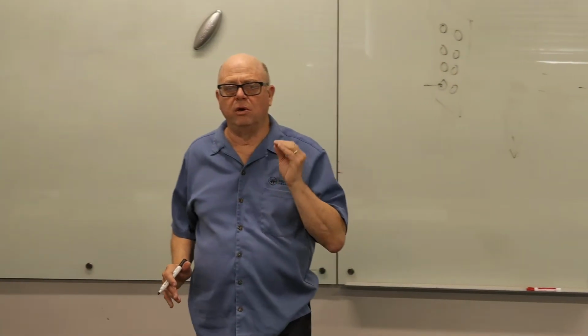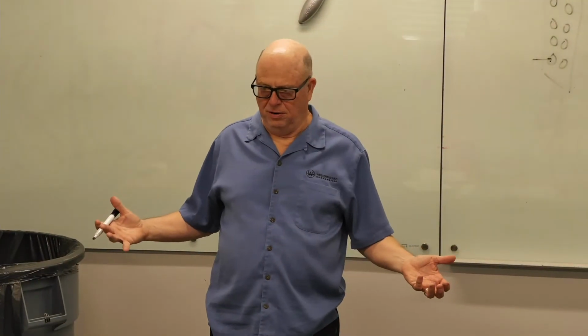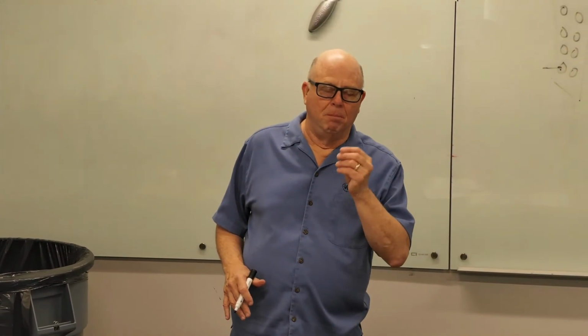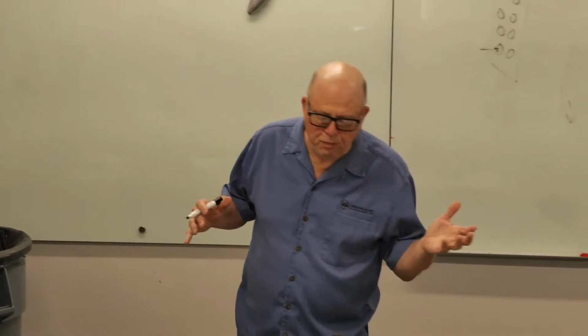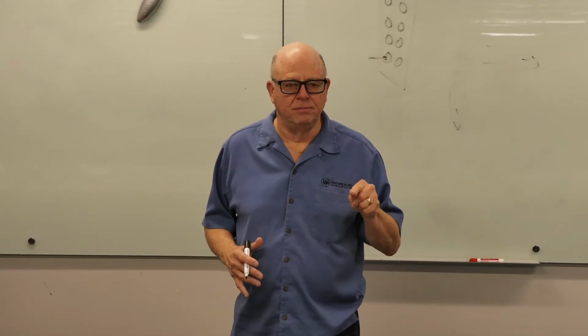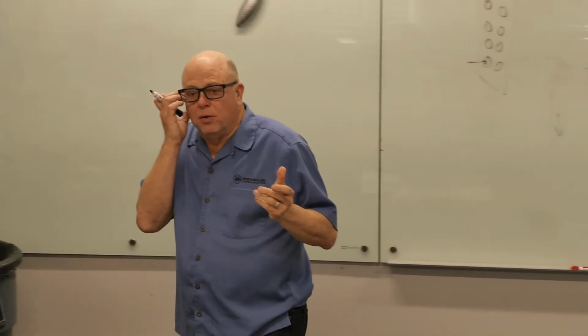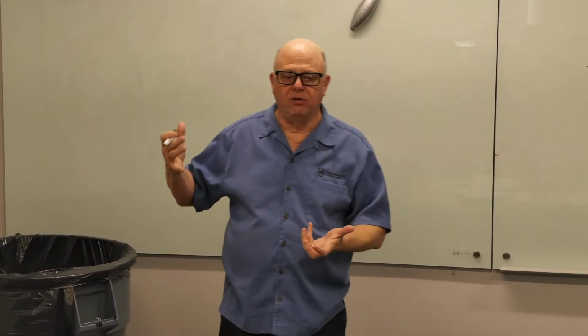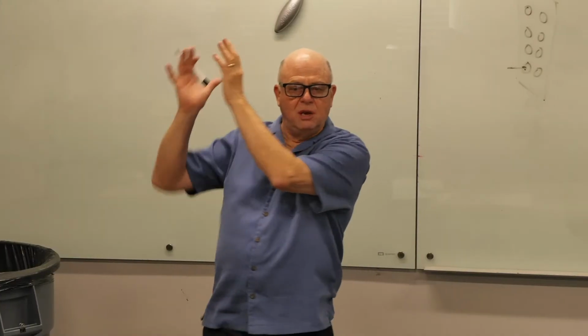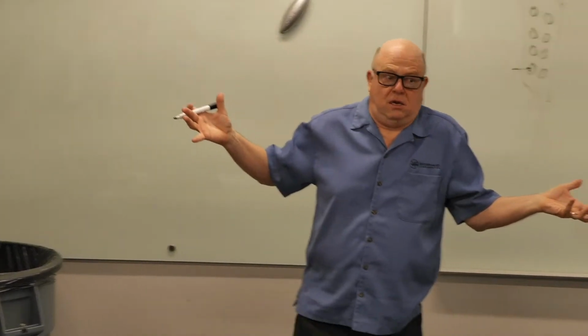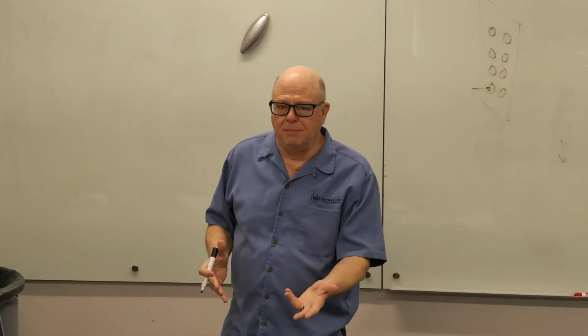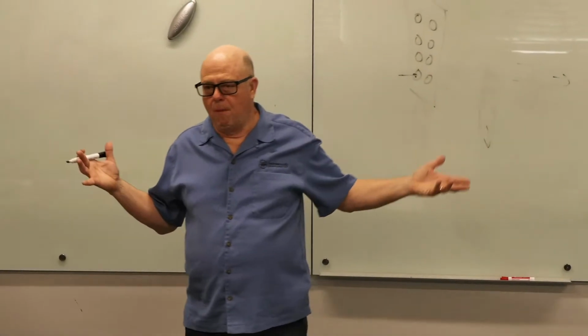The issue of an analog or a digital signal came up. We live in an analog world. Everything in our world operates in an analog manner. But most of our communication is digital. So in the controls world, we try to figure out, does it make sense to try to use digital to simulate analog, or do we just create an analog signal? A 4 to 20 milliamp signal or a 2 to 10 volt DC signal is an analog signal.